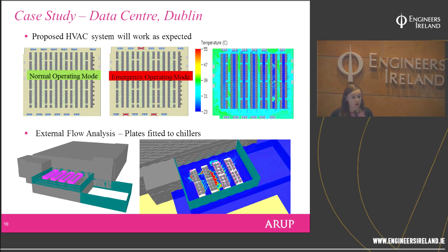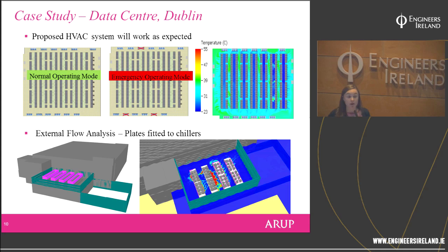In this particular example, we looked at the normal mode of operation with cooling units at the top and bottom of the data centre. We first assessed whether it would perform optimally with all units in operation, then considered an emergency situation where some cooling units might be turned off or broken. In both cases the data centre would be okay — the specified HVAC would perform efficiently without overheating.